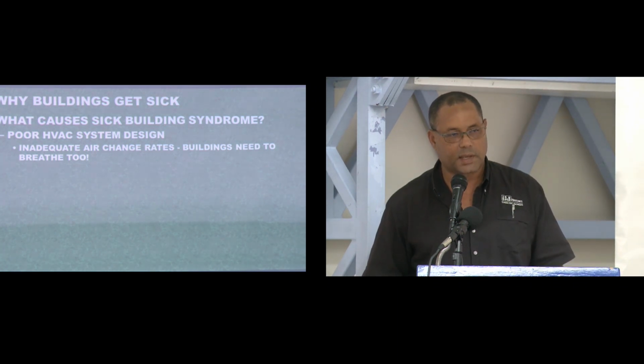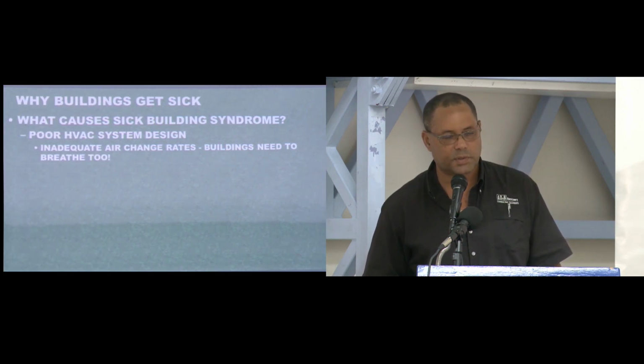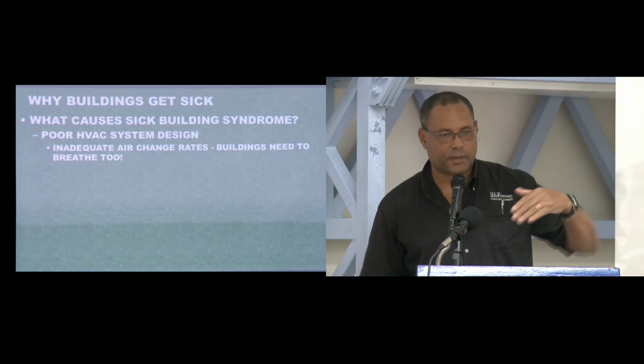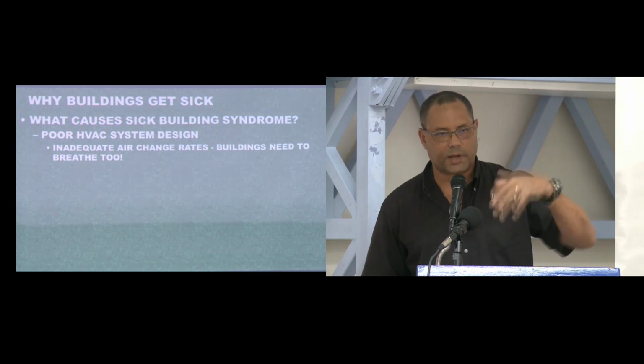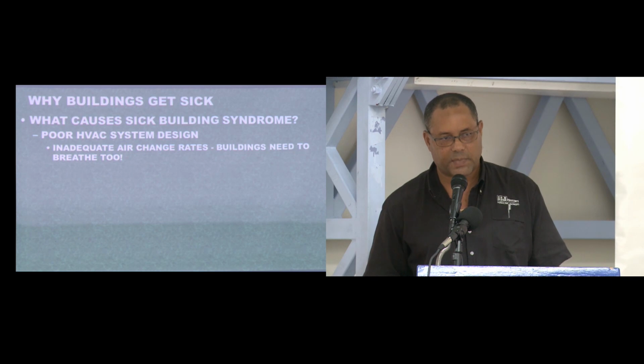I had a classic case of a building a few years back, a small industrial complex, where they had CO2 sensors on the outdoor air dampers. So the idea is that when your CO2 levels build up, the motors will drive the dampers open, allow air in, and then shut down. That's supposed to save energy. Only problem is that they had a large number of exhaust fans pulling air out of the building, which meant that when you open the front door, all the air flew in from the front door. Your CO2 levels never rose. The dampers never opened. And because we're in Barbados in a nice salty environment, those dampers froze shut. So you never got the air into the plant room. The air came in through the front door, through every open crevice in the building. It's just sucking all this dusty, moldy, hot, humid air into the building.